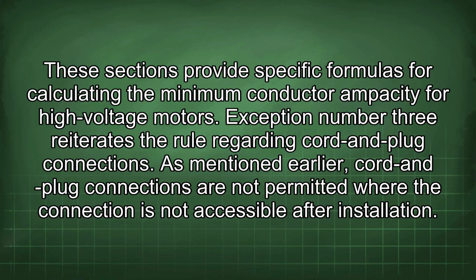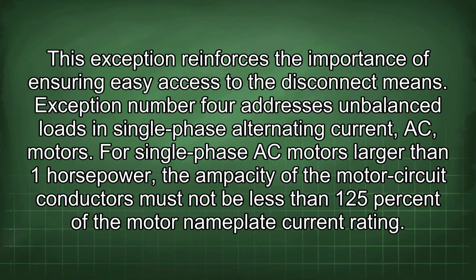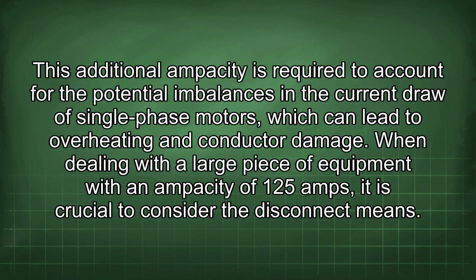Exception number 3 reiterates the rule regarding cord and plug connections. As mentioned earlier, cord and plug connections are not permitted where the connection is not accessible after installation. This exception reinforces the importance of ensuring easy access to the disconnect means. Exception number 4 addresses unbalanced loads in single-phase alternating current (AC) motors. For single-phase AC motors larger than 1 horsepower, the ampacity of the motor circuit conductors must not be less than 125% of the motor nameplate current rating. This additional ampacity is required to account for the potential imbalances in the current draw of single-phase motors, which can lead to overheating and conductor damage.